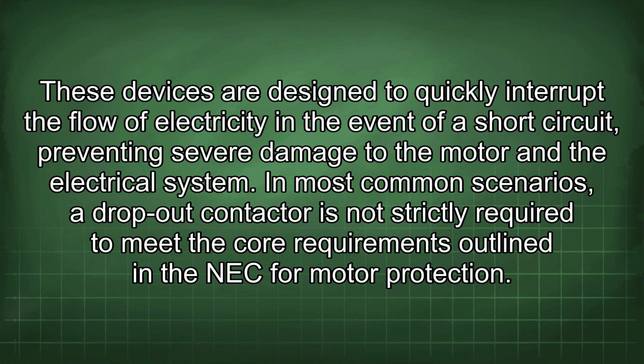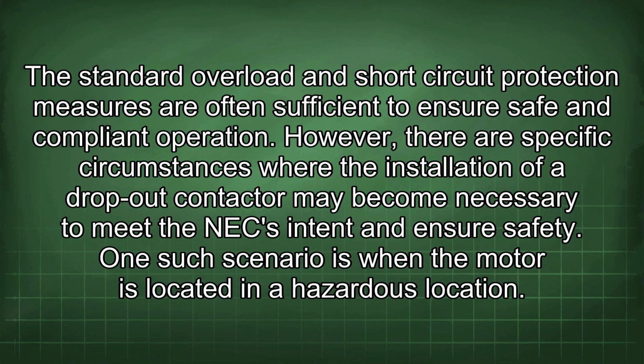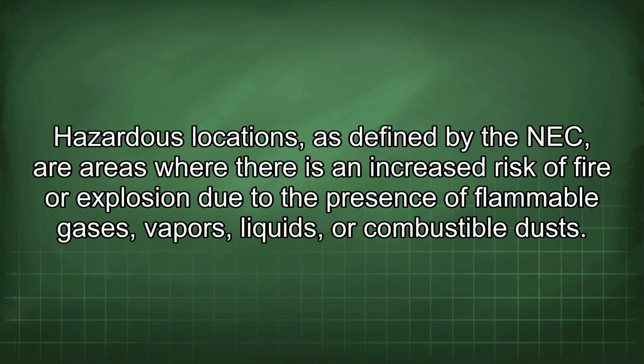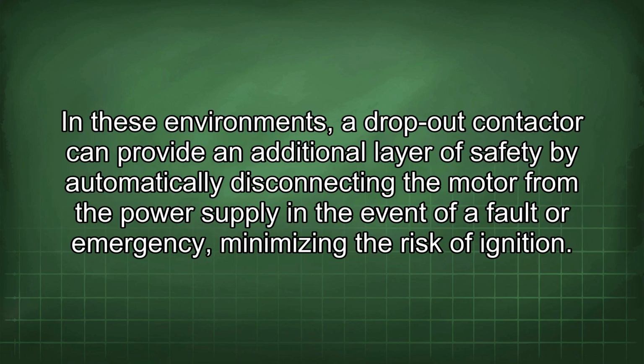In most common scenarios, a dropout contactor is not strictly required to meet the core requirements outlined in the NEC for motor protection. The standard overload and short circuit protection measures are often sufficient to ensure safe and compliant operation. However, there are specific circumstances where the installation of a dropout contactor may become necessary to meet the NEC intent and ensure safety. One such scenario is when the motor is located in a hazardous location. Hazardous locations, as defined by the NEC, are areas where there is an increased risk of fire or explosion due to the presence of flammable gases, vapors, liquids, or combustible dusts. In these environments, a dropout contactor can provide an additional layer of safety by automatically disconnecting the motor from the power supply in the event of a fault or emergency, minimizing the risk of ignition.